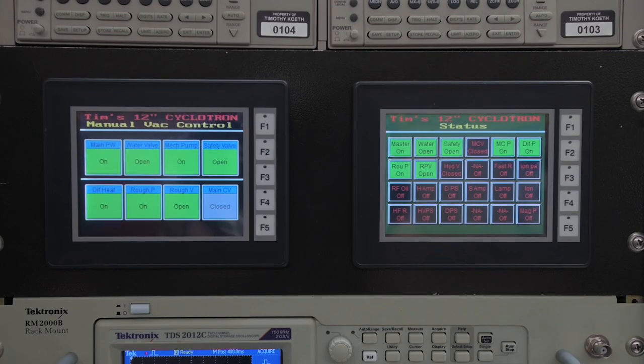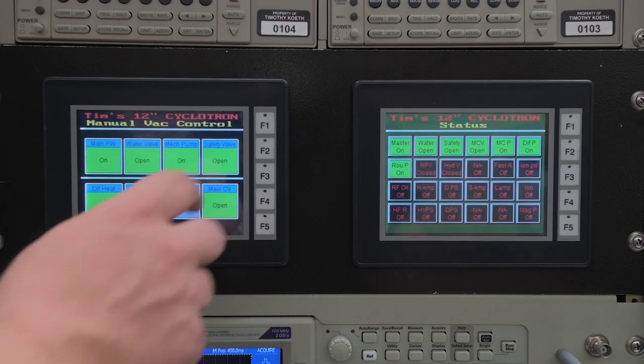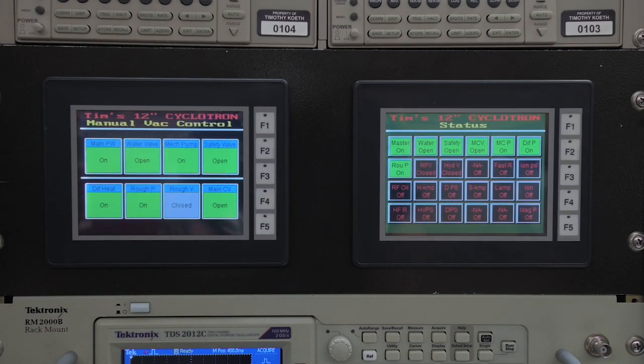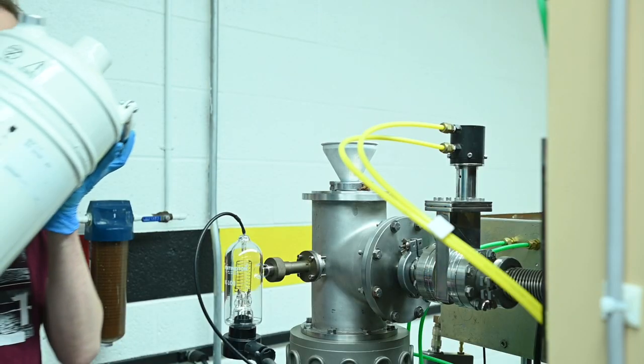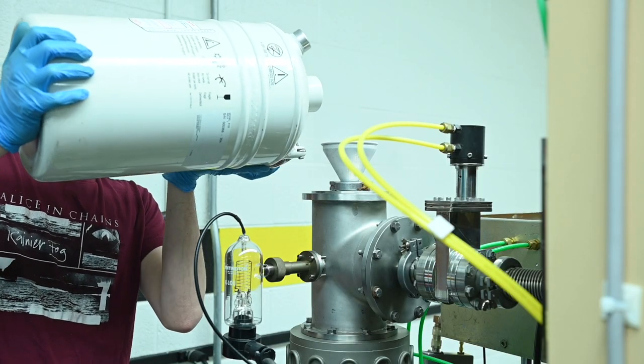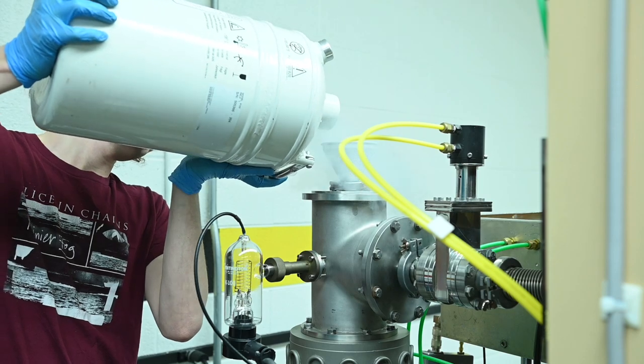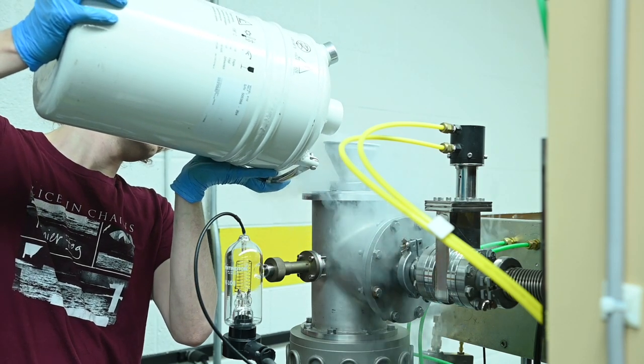The initial rough pressure of the vacuum system, as achieved by the rotary vane pump measured by the Pirani gauge, is just below 100 millitorr. The roughing valve is then closed and the main chamber valve opened, connecting the diffusion pump to the cyclotron chamber and disconnecting the direct line to the roughing pump. Liquid nitrogen is then added to the cryogenic trap above the diffusion pump.